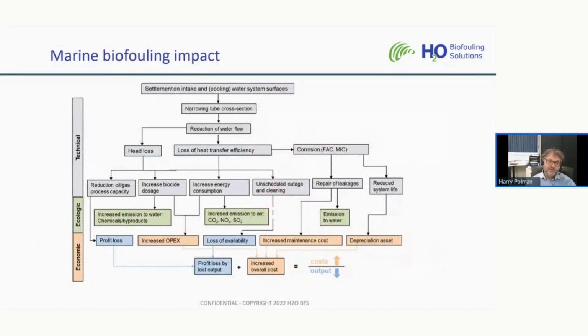This is a nice schematic overview I once created to give some insight into what will happen when you get settlement of marine fouling organisms in an intake pipe. Well, first of all, you get a technical impact. The cross section of the pipe will be narrowed. A reduction of water flow will happen. You will get head loss. In the heat exchanger condenser, you get a loss of heat transfer efficiency, and biofouling can also result in corrosion, flow accelerated corrosion or microbial induced corrosion. This has a big impact on the technical reliability of the utility itself and results in ecological, environmental impacts.